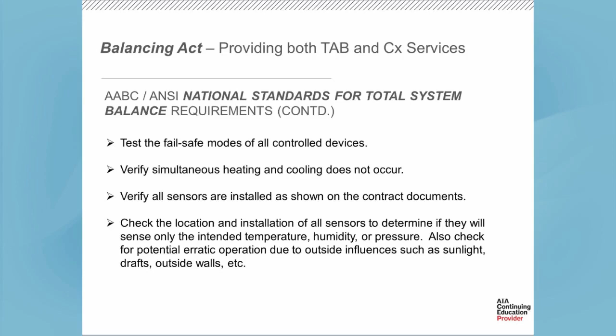So we're going to say in our firm, what's the best way to do this? And we argue that the testing and balancing firm should handle the terminal units and handle the sensor and point verification on the project, and then turn it over to the commissioning provider, whether that team is within their own firm or whether it's an external team, because we feel like that's the most efficient way to go about and verify everything. And so with that being said, what should the testing and balancing firm check on the terminal units? They should verify the calibration of all the airflow sensors and ensure the terminal units are set up correctly. I don't think anybody argues with that. That is the TAB firm's role.